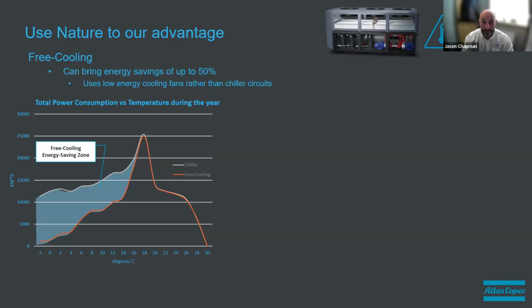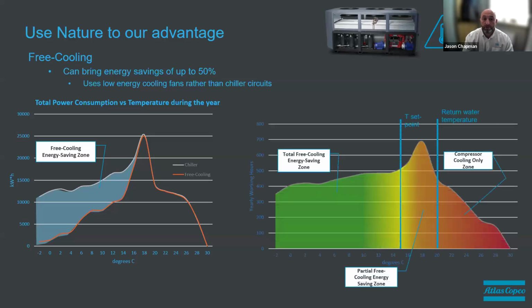We can use it probably eight months out of the year or so. And obviously, by using nature to our advantage that way, we reduce the energy spend and also reduce the carbon impact. On the next pictorial, you can see the highlighted green zone is free cooling, 100% free cooling, which we can get for quite a few months out of the year. We then also have partial free cooling, and then down to the compressor cooling only, which is the chiller side of the chiller.